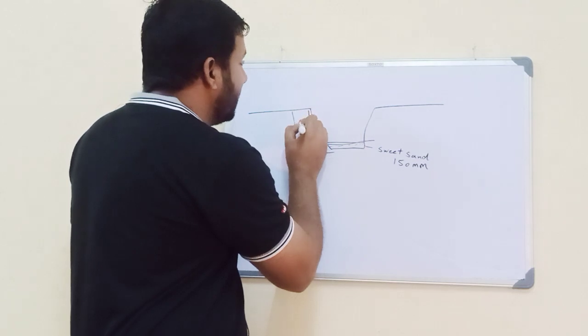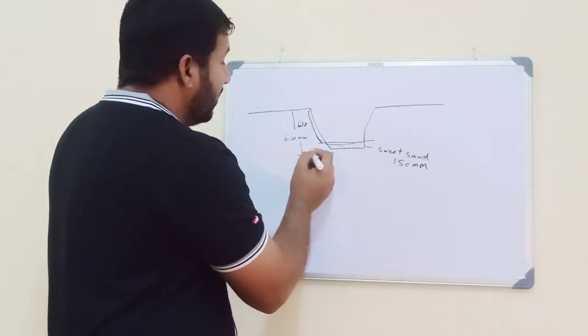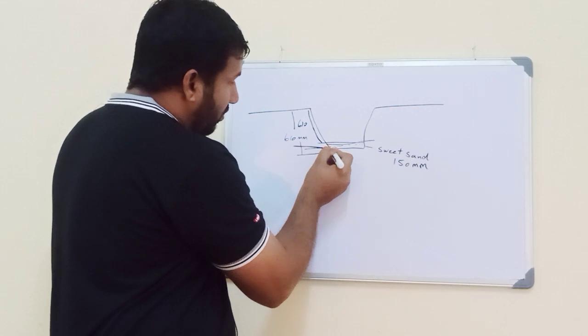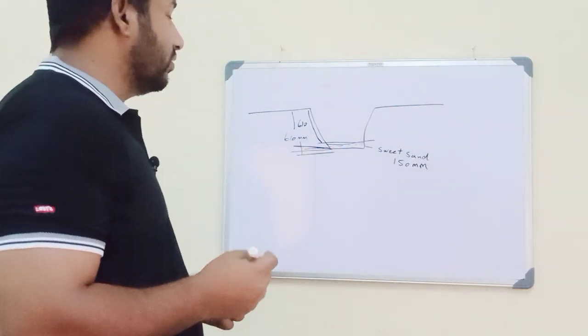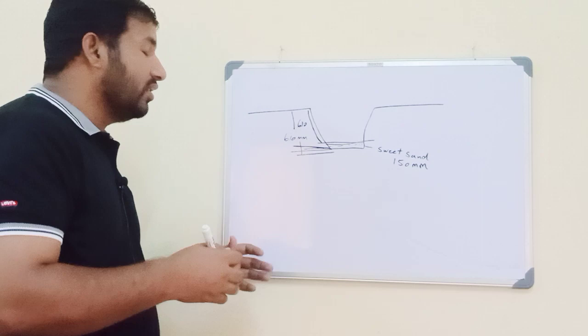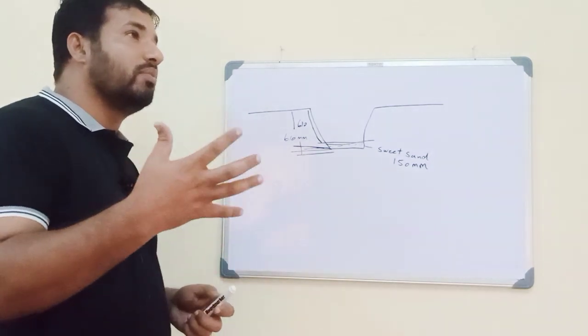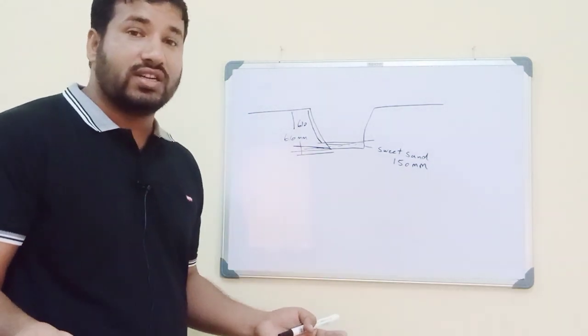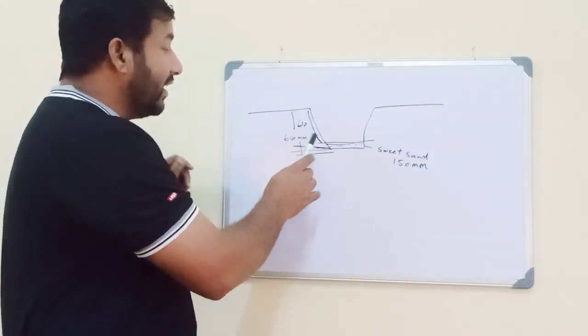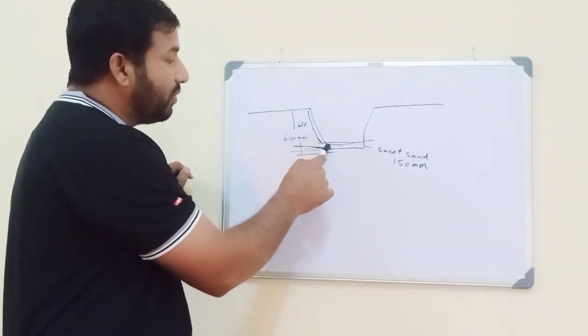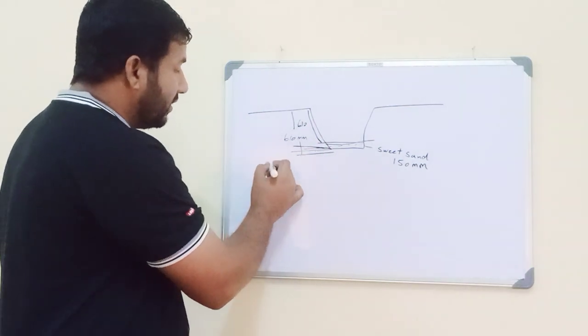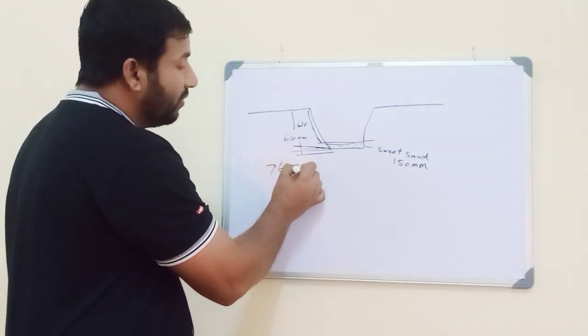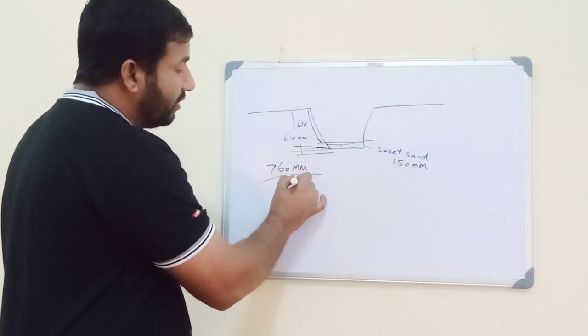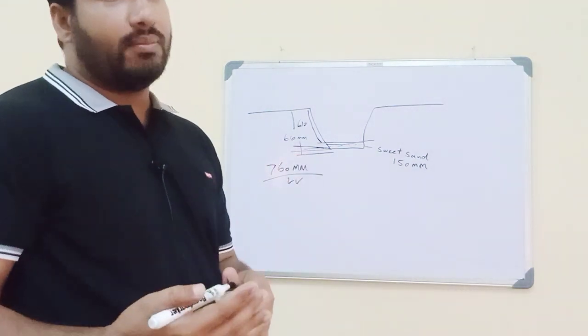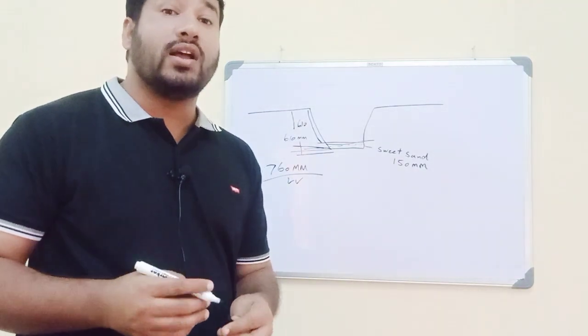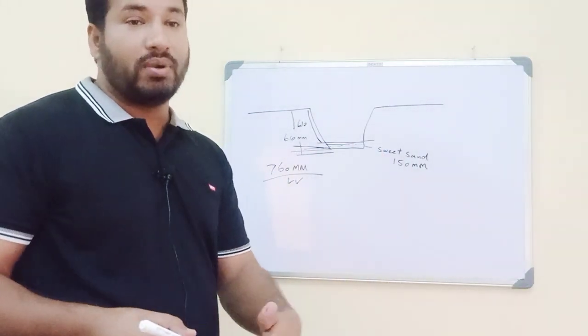From this cable we actually need 610 mm or 920 mm - it's not from here, okay, this is a very important question. Sometimes our friends read the standard and just remember LV cable depth is 610 mm. No, that depth starts from the cable, so 610 mm plus 150 mm becomes 760 mm trench depth for LV cables. Remember that. Same for MV - 920 mm plus 150 mm, you have to add that.